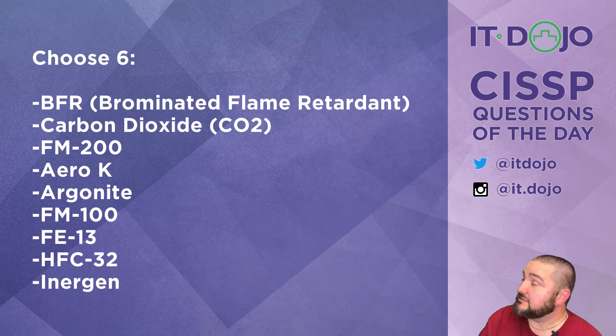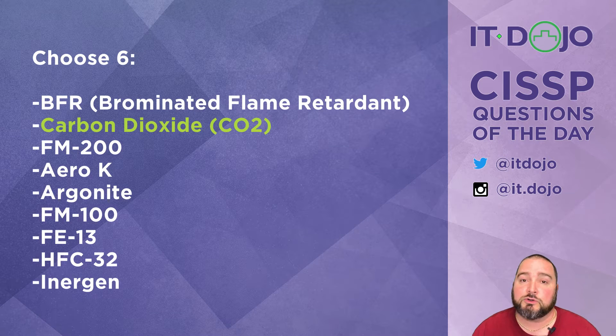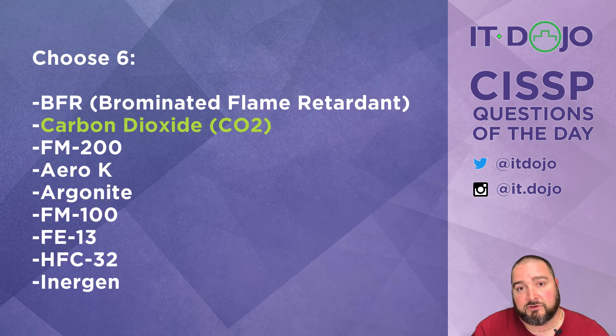Next on the list is carbon dioxide. Carbon dioxide is excellent at putting out fires and it is approved by SNAP for doing so. It does however have a caveat that you must follow OSHA's regulations as they relate to fire suppression — there's a link below pointing to what OSHA has to say on that. The problem is that carbon dioxide and people don't get along well, so you can't pump mass quantities of carbon dioxide into an environment and expect people to live. That's really where OSHA's focus is.